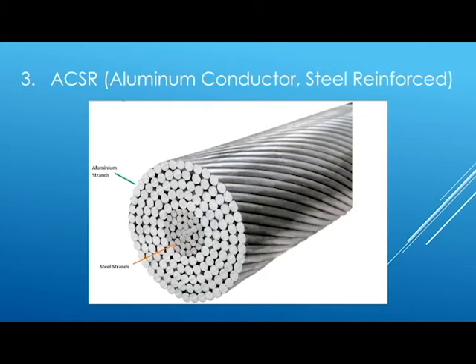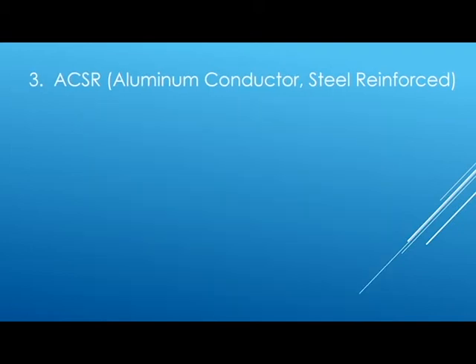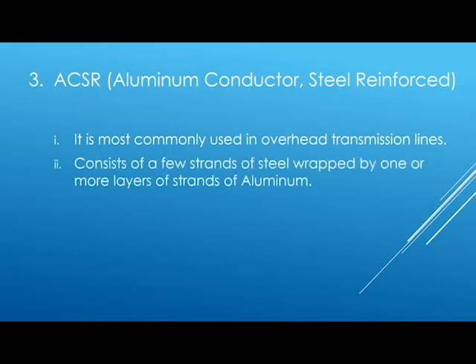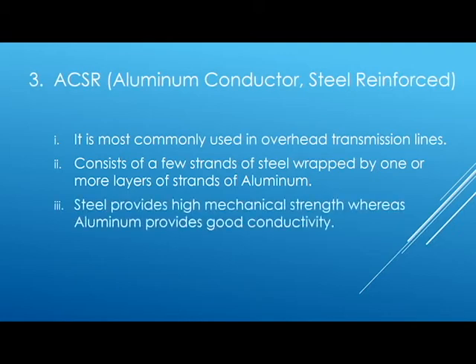Next is ACSR conductor, which stands for Aluminum Conductor Steel Reinforced. As its name suggests, ACSR is different from other conductor types because its strands are made of two different materials: steel and aluminum. ACSR is the most common type of conductor used in overhead high voltage transmission lines. It consists of a few strands of steel which are wrapped by one or more layers of aluminum strands.